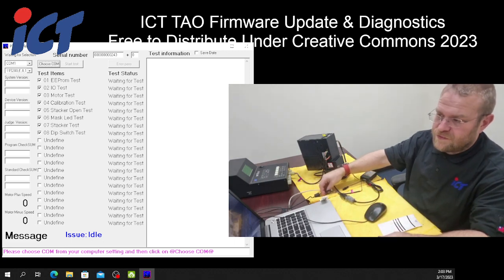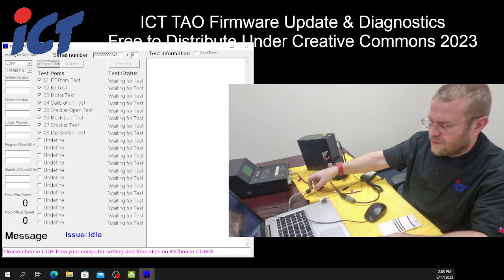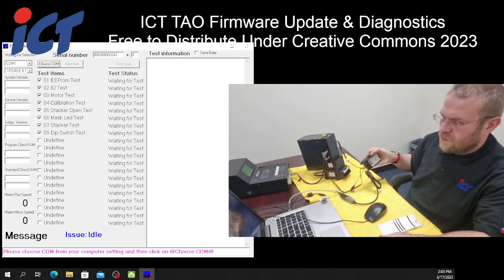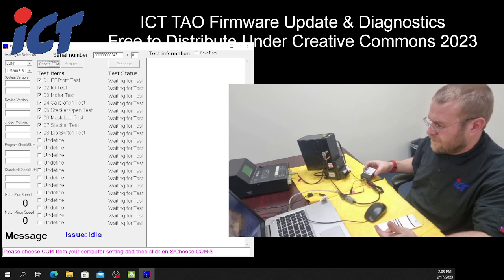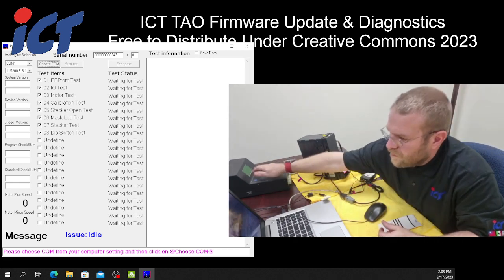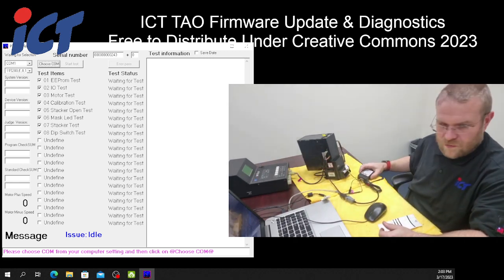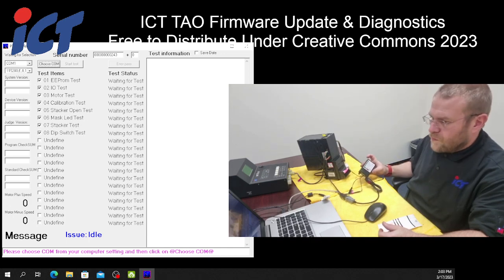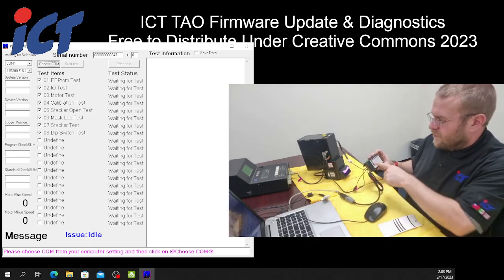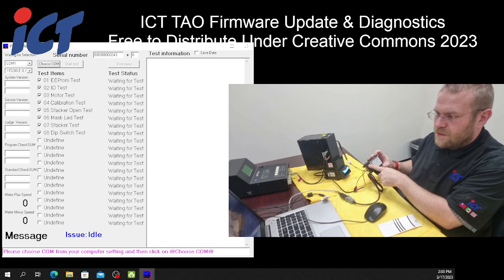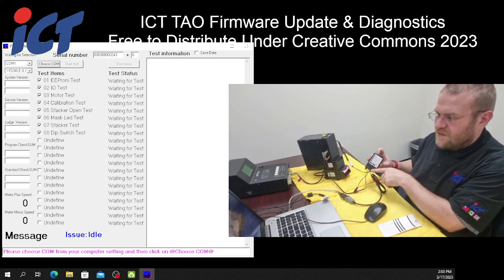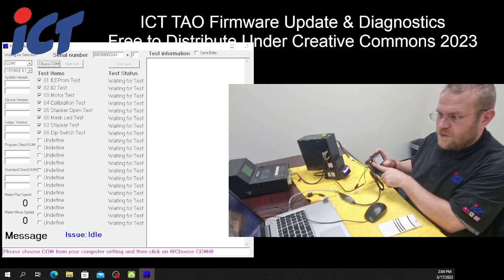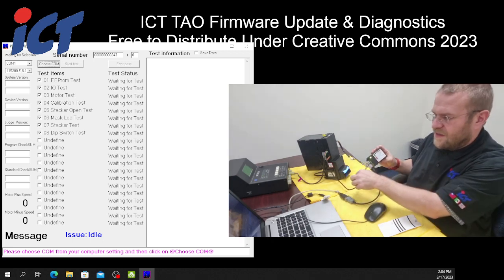So in this example, say you forget to power your programmer externally. When the TAO is turned off, there are no lights on the programmer. When you power the programmer, it's going to be in green mode. And when you turn it off, it won't stay in the yellow mode that you set it to if it's not externally powered.